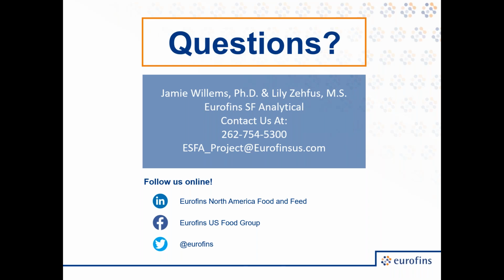Great, thank you for that answer. And do you have a favorite SPME needle for off flavors? Well, our go-to SPME fiber is a divinylbenzene carboxen on a polydimethylsiloxane fiber. It's also known as the gray fiber when you look at the color coding. And this is our go-to fiber for volatiles and semi-volatiles.